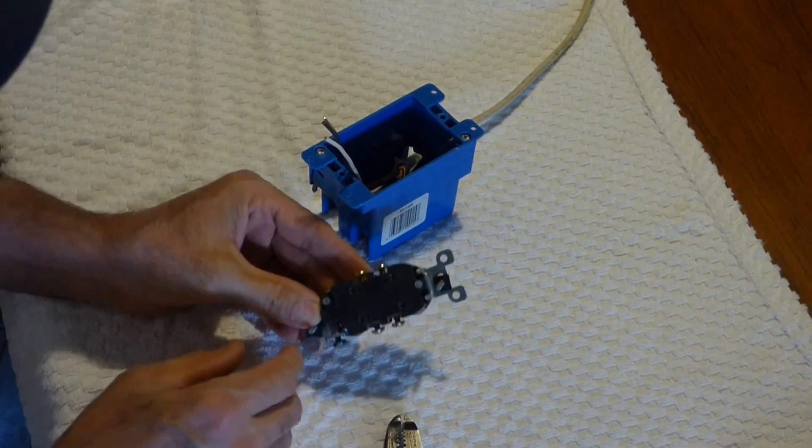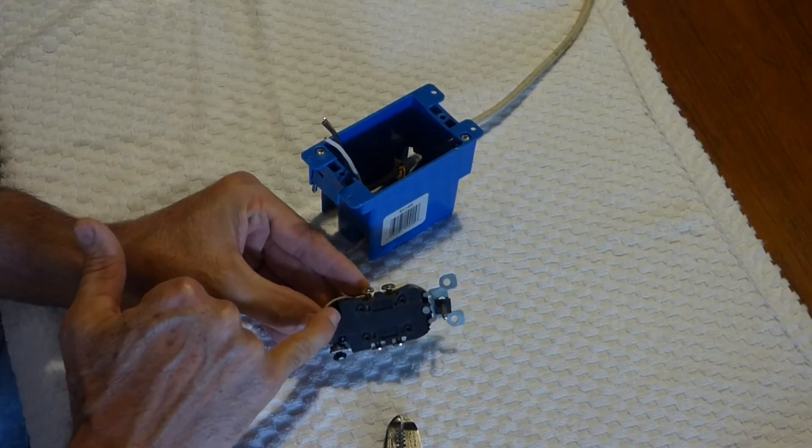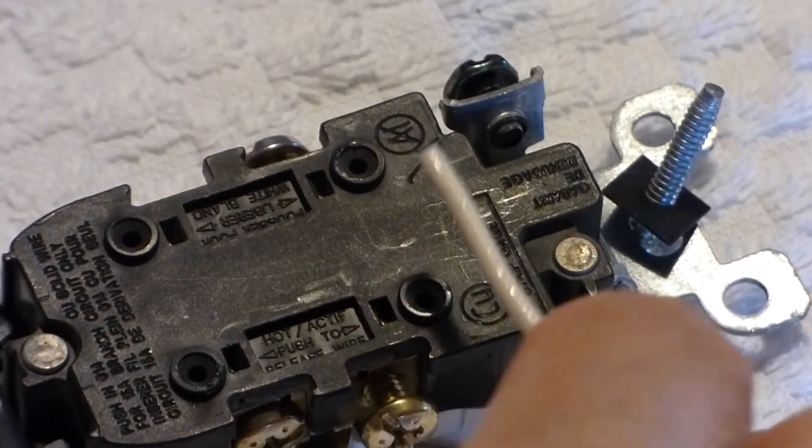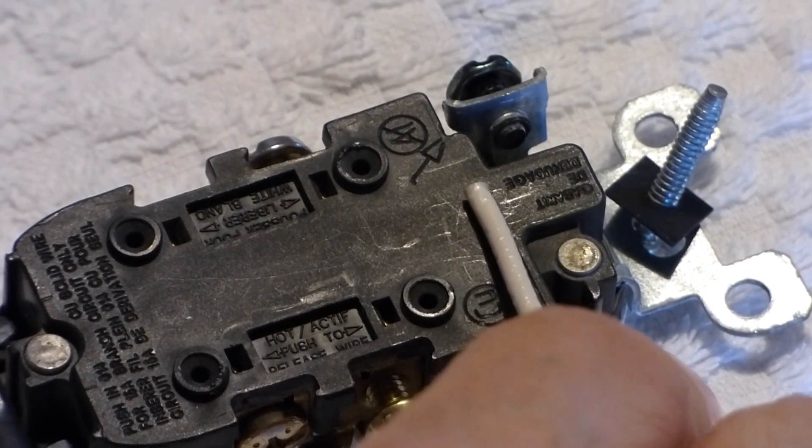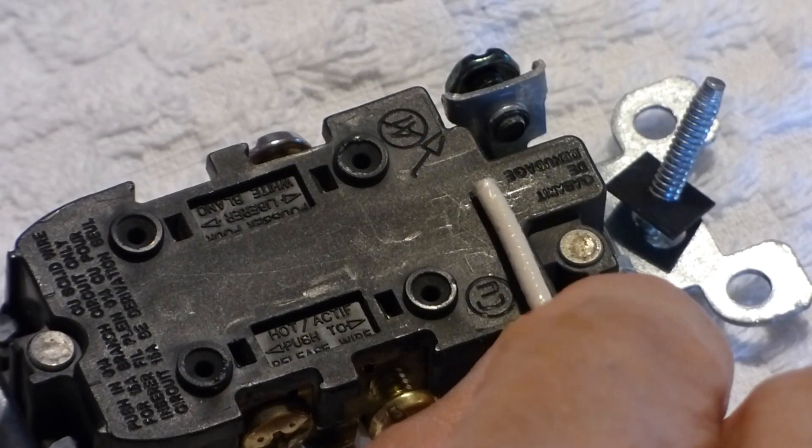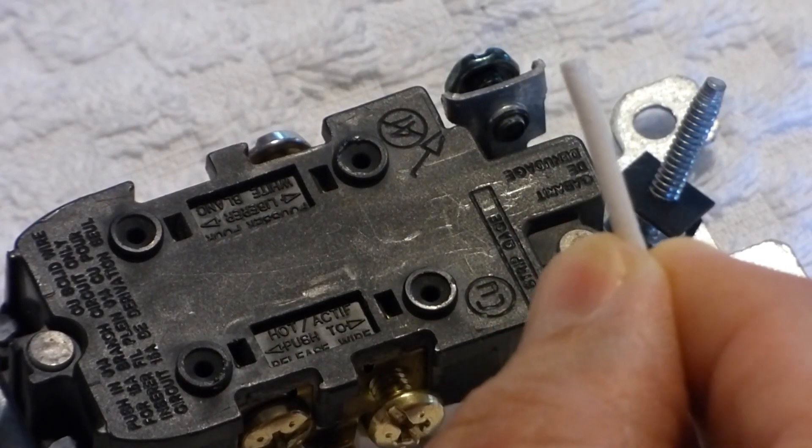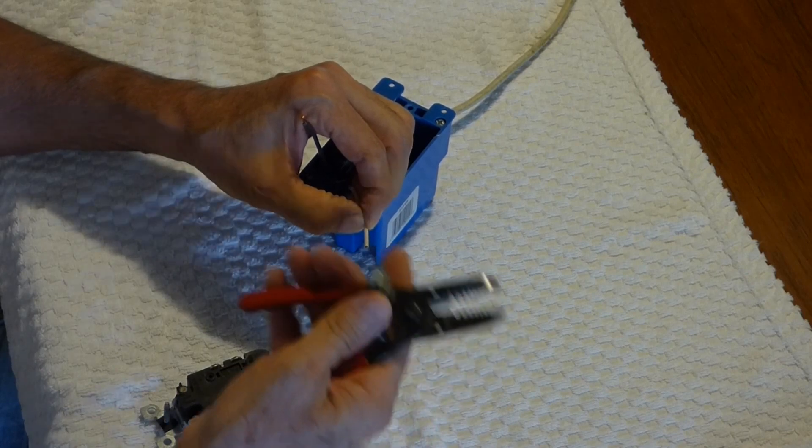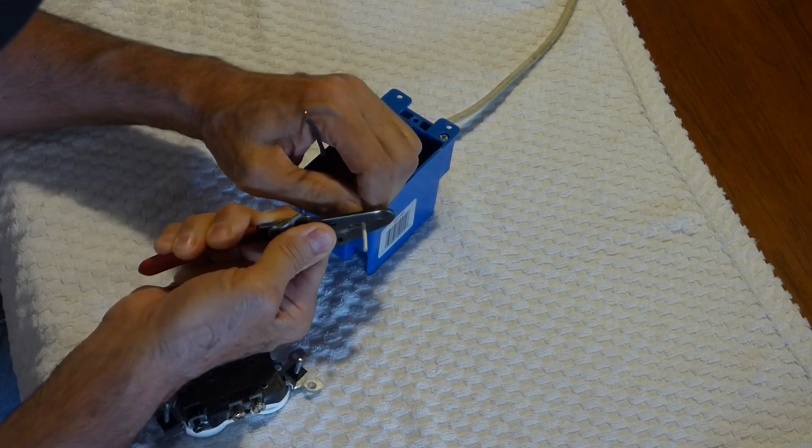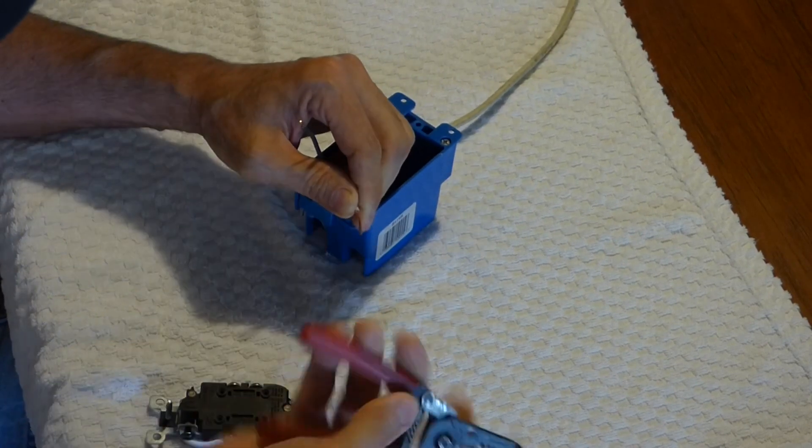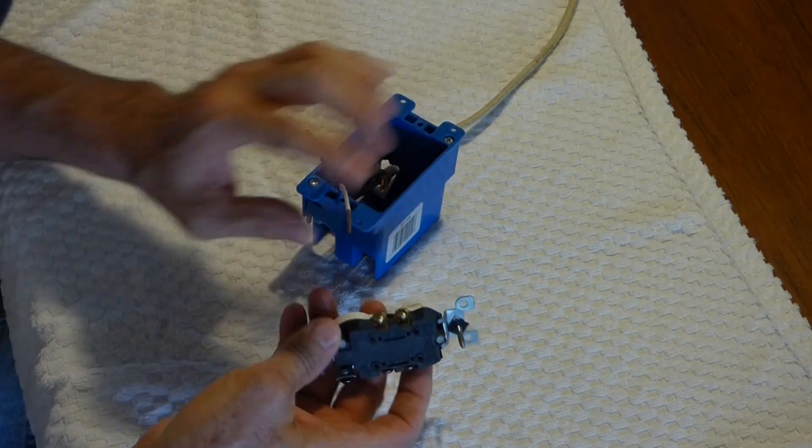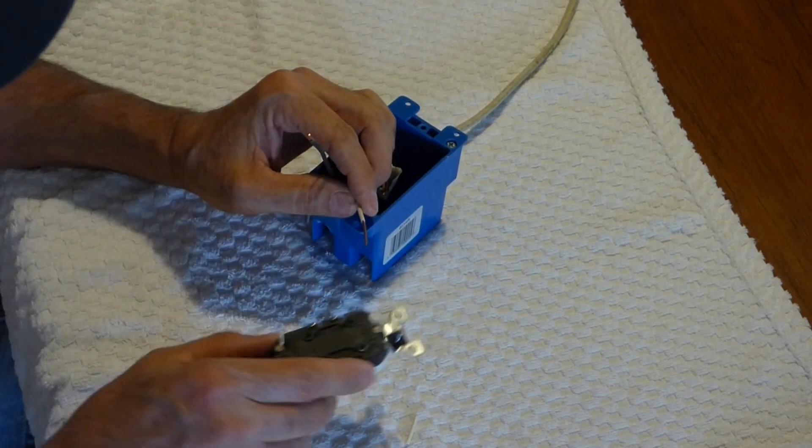Now on the back of the receptacle, and some will be indented, is a stripping gauge. It's 5 eighths of an inch long. What you do is take your wire, put it against the stripping gauge, and you can hold your finger in place. Take your wire stripper, line that up with the 14, wrap it around, hold the wire, and pull that off. That gives you the perfect length for securing the wire onto the receptacle.